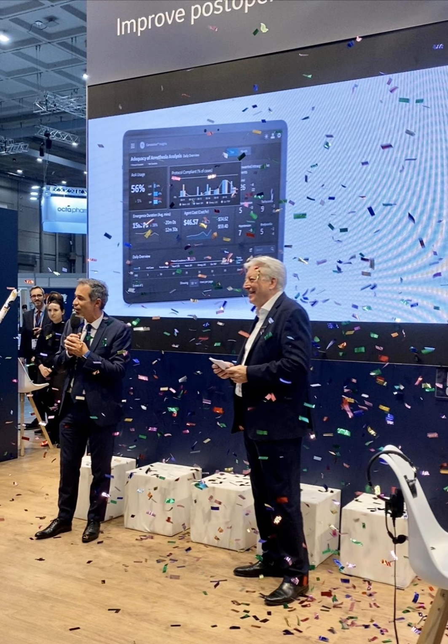So if you are in the OR, the ICU, the PACU, the general wards, you're going to have the same environment, the same type of product, but depending on the level of acuity you're looking for, you might have different software loaded in your monitoring system. So it brings you a lot of flexibility, and we are coming up with a new concept that we call flex acuity. You can flex up, you can flex down, and you can adapt to a pandemic situation, to a variation in your hospital. It also protects your investment, because with a long-term strategy, investing in a monitoring platform, you're going to keep it for the next 10 years. So you also have some flexibility on this aspect.